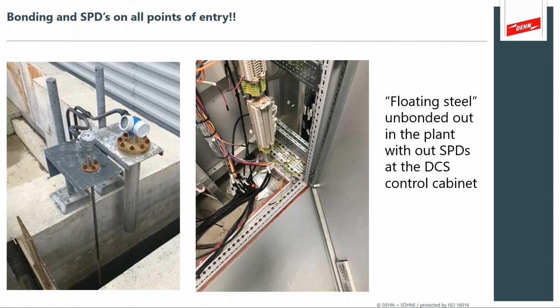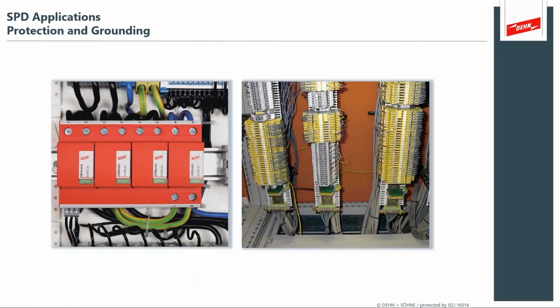A lot of times I've heard designers say, well, I don't want to bond this metal because if there's a lightning strike, it'll be affected. If there's a lightning strike, it'll be even more affected because it's not bonded, which now introduces a huge voltage ground potential rise into this circuit. And in this case, we're able to trace the wires back into a data control system inside of a cabinet, and there's no surge protection devices installed here either. So in this case, the actual solution to a problem like this is to put bonding on this metal, surge protection devices at the flow meters, and surge protection devices inside of this control cabinet. So remember, you're looking for all those back doors into your electrical control systems. So there's a wide variety of surge protection devices available for both the AC protection and the data protection inside of such an electrical control panel.